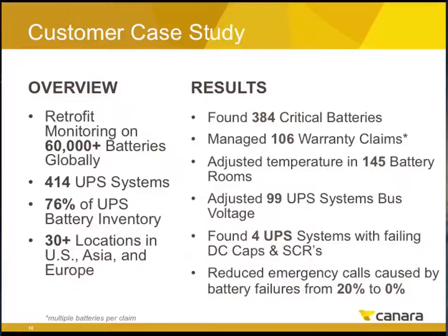On the right side, you can see the kind of things we find when we implement our technology and services. We found many hundreds of bad batteries that needed to be replaced, and we managed a ton of warranty claims. One thing that's not well known is when you go to a battery vendor with a warranty claim, one of the first things they'll ask is: did you maintain the right float voltage, the right temperatures, did you treat the battery properly? Because our system takes 4 data points a day and logs all of that data, when we present a warranty claim to the battery vendors we work with, we typically easily facilitate that and get it paid with no problems.